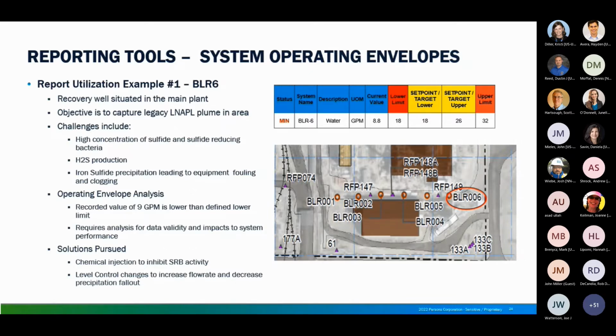As we rolled out these operating envelopes, we initially put this particular system on a preventative maintenance cleaning frequency of about 6 to 8 weeks. As a result of continuing to pursue solutions based off of the feedback we were getting from our operating envelopes, ultimately those level control changes, which stuck, allowed us to extend the time before clogging would impact system performance to about 12 weeks. So we roughly doubled the amount of runtime we get out of that particular system.